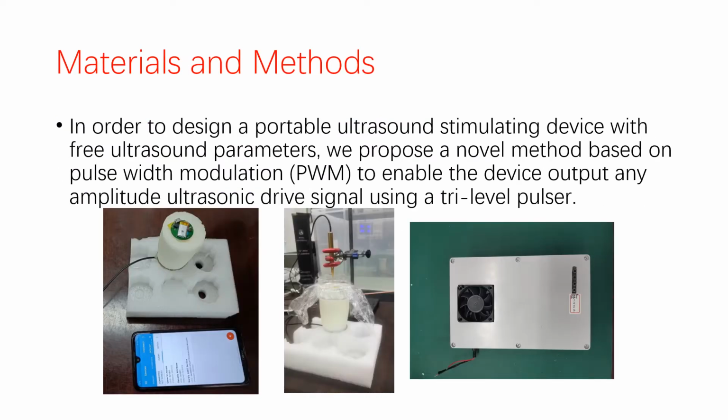In order to design a portable ultrasound stimulating device with free ultrasound parameters, we proposed a novel method based on pulse-width modulation to enable the device to output any amplitude ultrasonic waveform using a 3-level pulser.